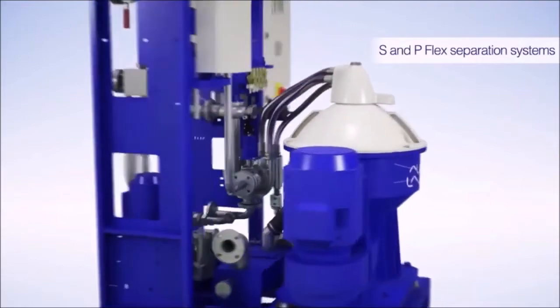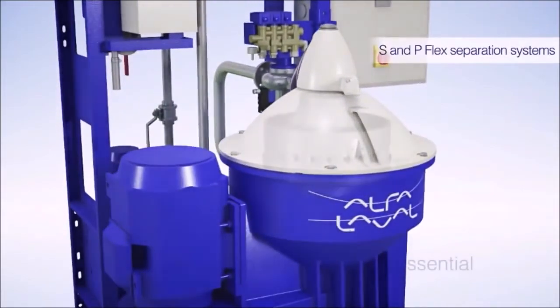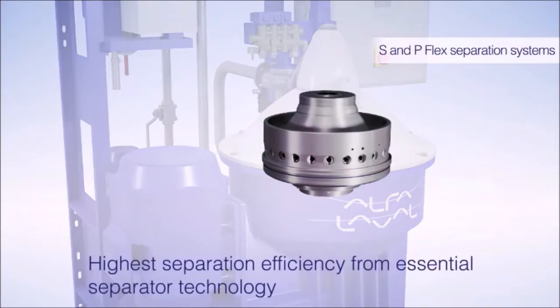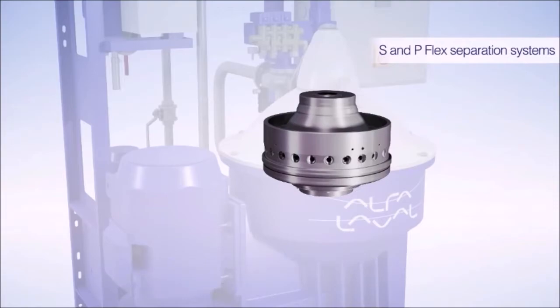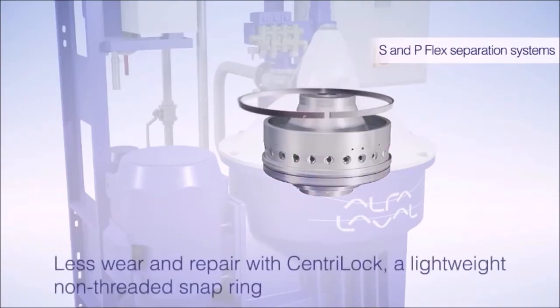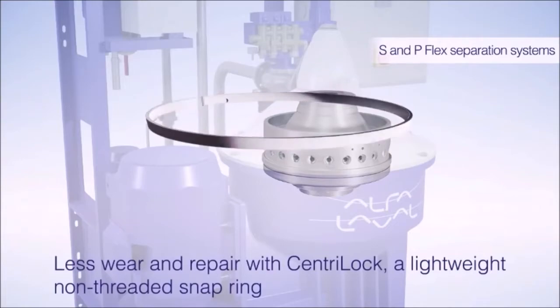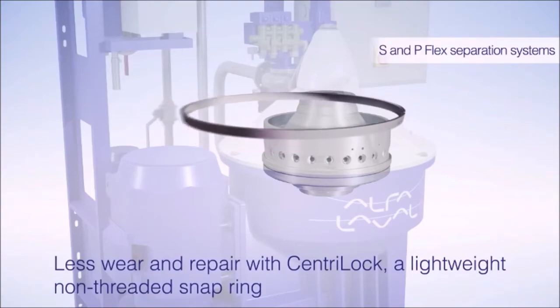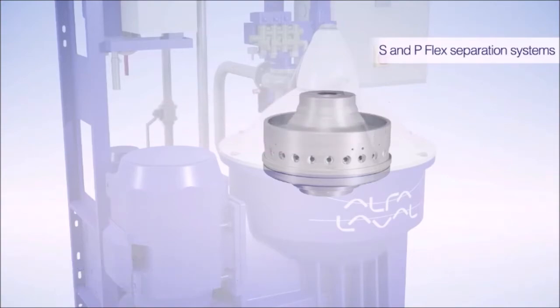Difference between purifiers and clarifiers: in a purifier, the centrifugal force is used to separate two liquids, so it is known as purifying, and the process uses a dam ring. In a clarifier, the difference is that the centrifugal force is used to separate a small amount of water from oil, so it is known as clarifying, and no interface or line of separation between the oil and water is created, since no dam ring is used.